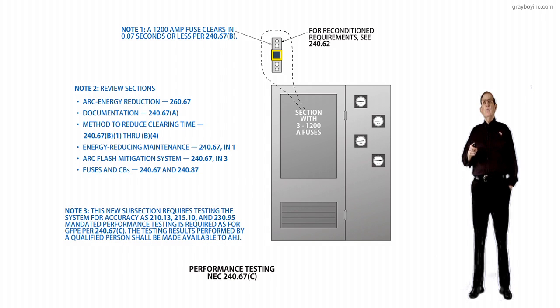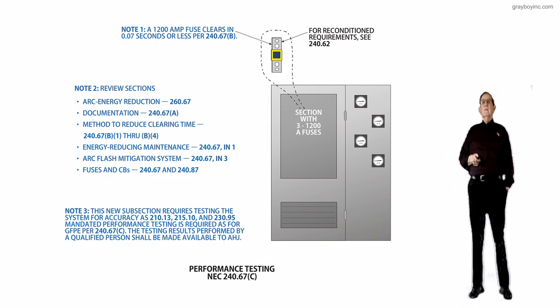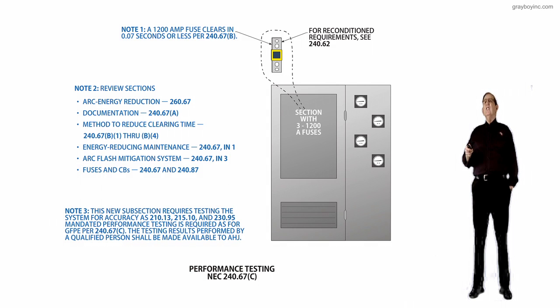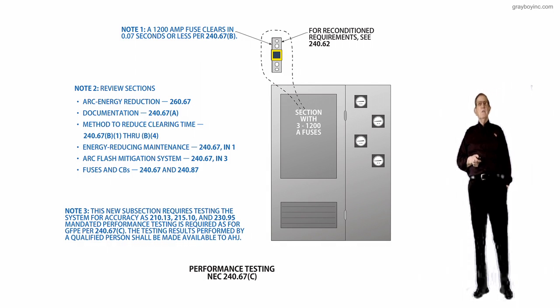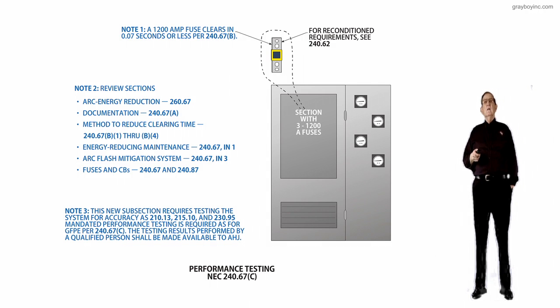Now, the first note, we've talked about that. It says the 1200 amp fuse clears in 0.07 seconds or less per 240.67(B). And we know for reconditioning requirements, we'd see 240.62, if that's even permitted or not. Now, Note 2 says to review the following sections: arc energy reduction, and we go to 240.67, and it says this fuse can be used for the purpose of reducing the time the current can feed the arc. Documentation is required in (A). The method to reduce clearing time is 240.67(B)(1) through (B)(4).